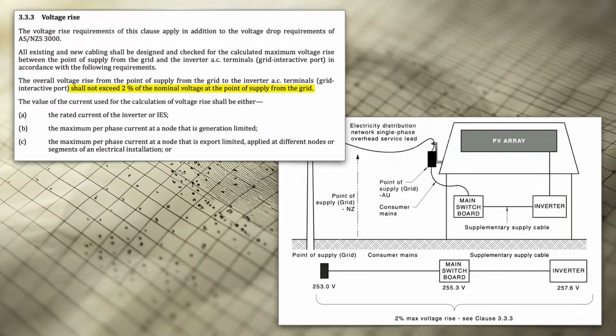supply requirements from the DNSP or lines company. So they're required to keep voltages to a residence within a certain range. For instance, your neighbour might not have solar, but they may be experiencing high grid volts because everyone else in the street has got solar and exporting at the same time. Now, the way to limit that is to reduce the voltage rise between the output of the inverter and the point of common connection.